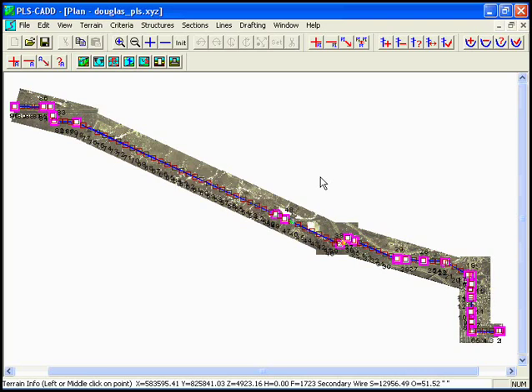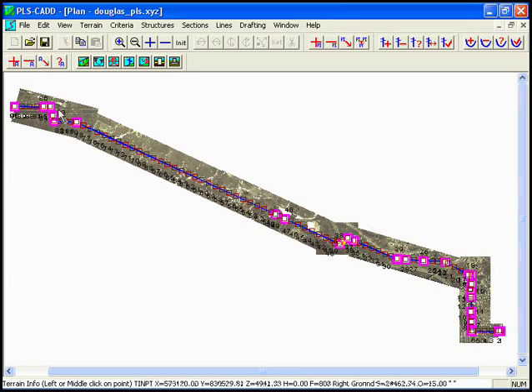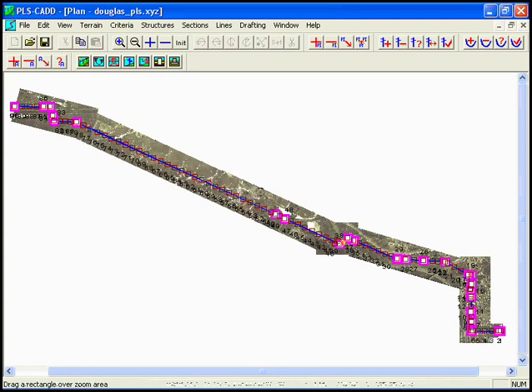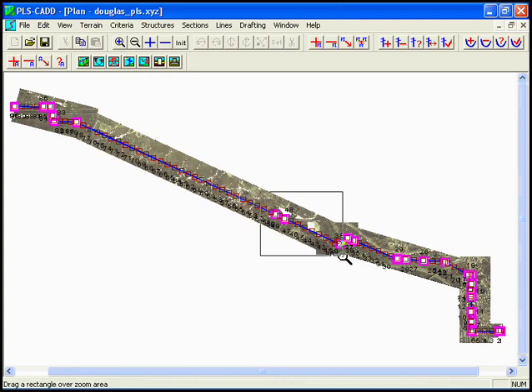PLS-CADD can be used to calculate the clearances between the phases of the same circuit or different circuits of an entire transmission line. In this example we have a transmission line that's a little over five miles long, 115 kV with the distribution under build, and we'll use this to calculate the clearances along the phases.